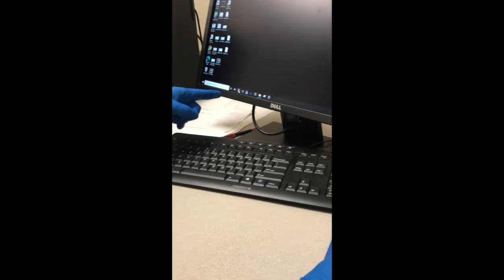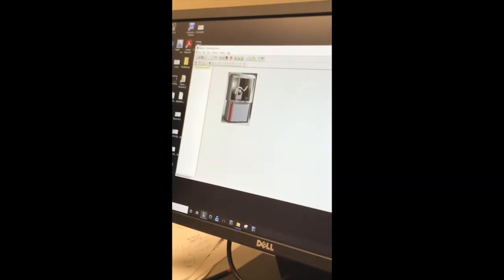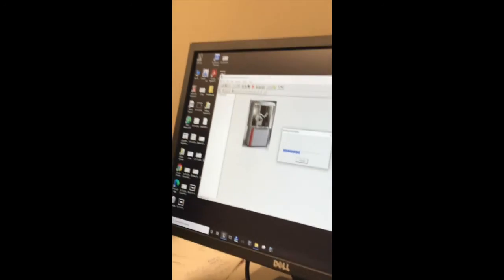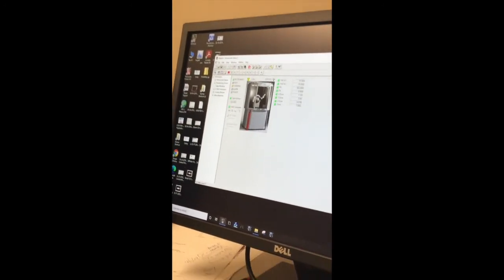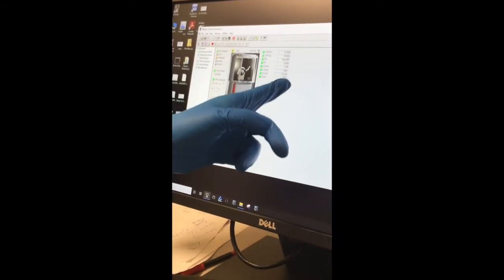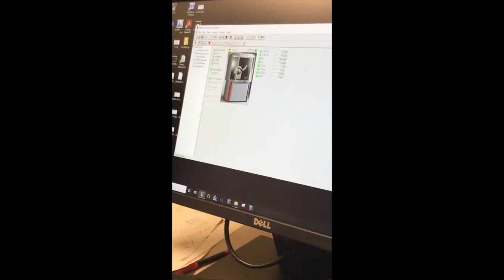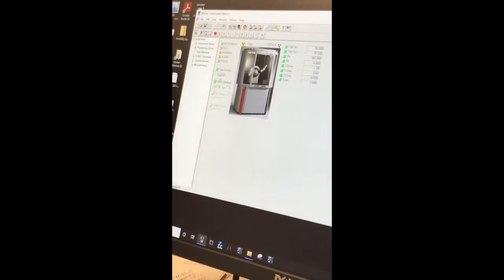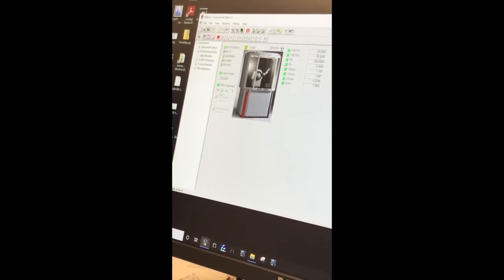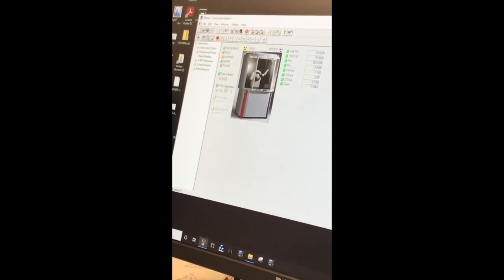Okay. So important. The apps or programs that we use, we have on the bottom here. The first one is this. It's called the D8 Tools. Double click. So the tools come on, and we click online status, and then over here we refresh the connection to get the information. Wait for it. Okay. So this indicates when this is green and you see a bunch of decimal points over here, most of them have 4 decimal points. That means these drives are good, right? And then also the tube is closed, right? And then the X-ray generator should be 20 kV and 5 milliamp. That's the standby position. Okay, now we confirm that everything seems to be okay hardware-wise.